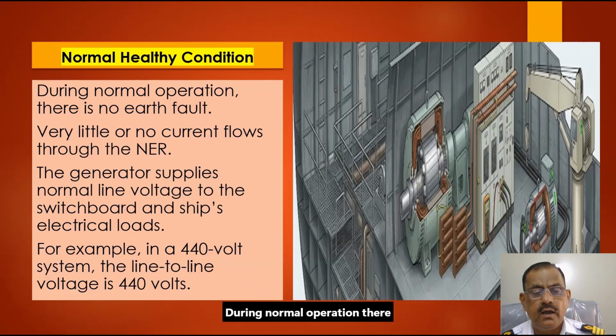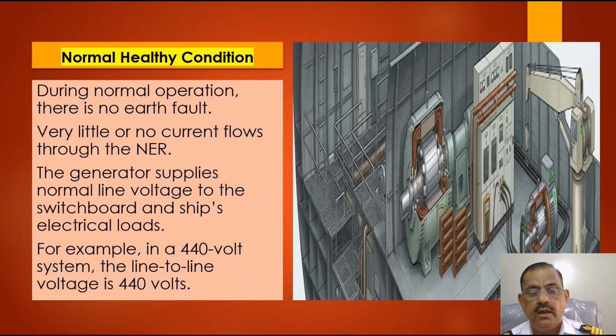During normal operation, there is no earth fault, so very little or no current flows through the NER. The generator supplies normal voltage to the main switchboard and all connected loads. For example, in a 440 volt system, the line-to-line voltage is 440.